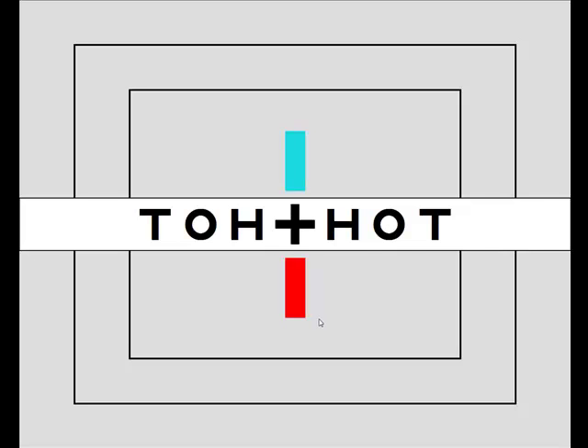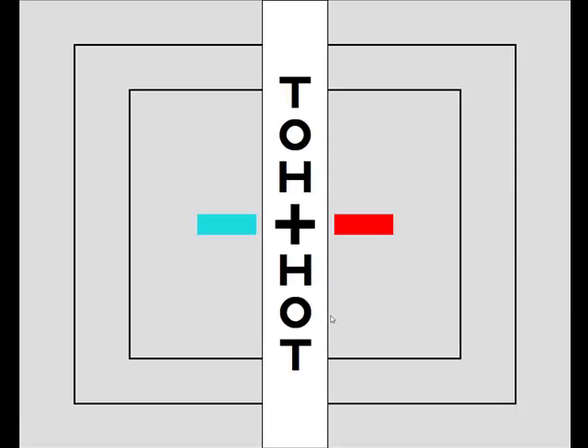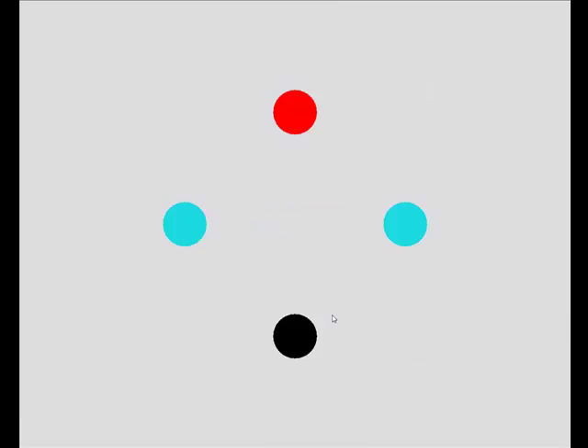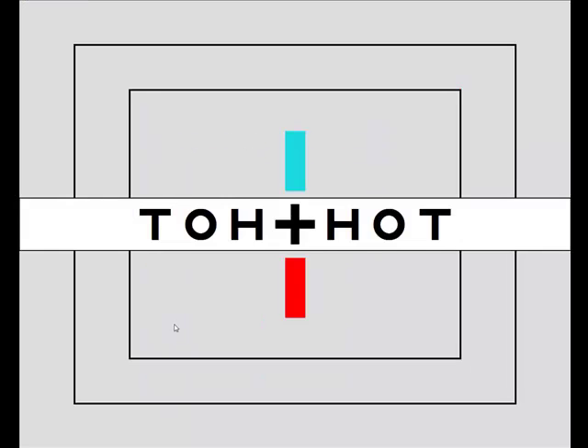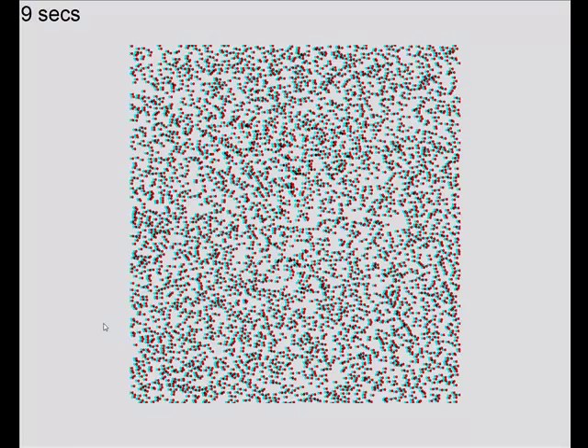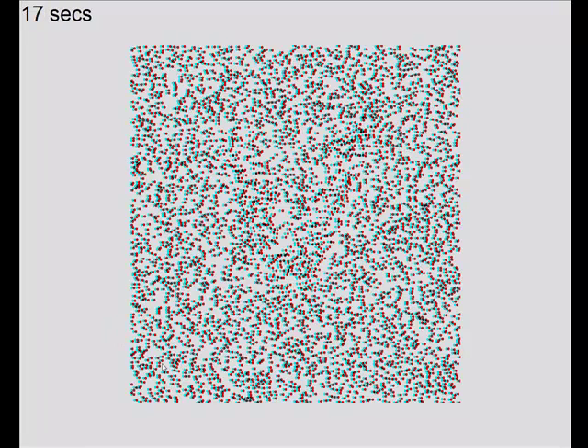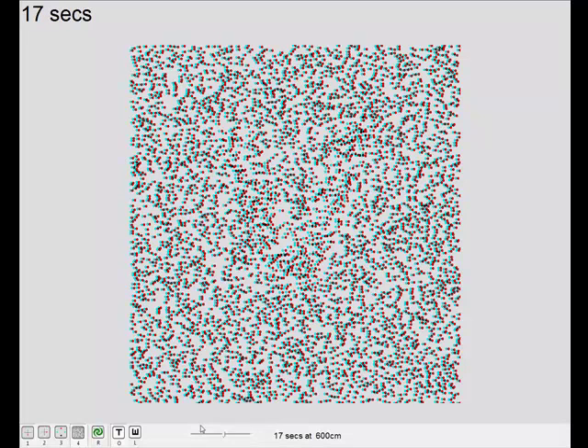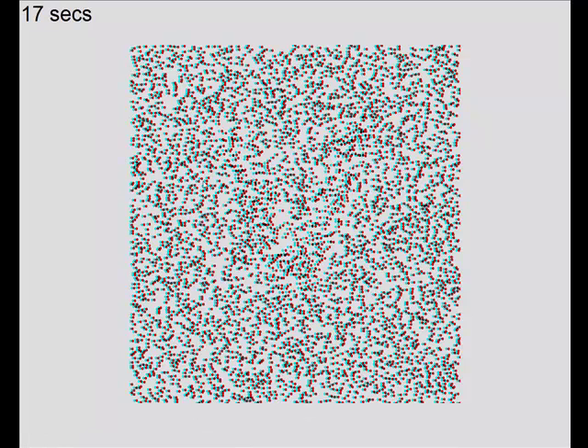This is for measuring horizontal fixation disparity, vertical fixation disparity, the Worth Four Dot test. And this is a distance random dot stereogram. If the patient is wearing the red and green visors, they'll see a shape standing out from the screen. These are generated dynamically. By using the up-down arrow keys on the keyboard or the scroll bar in the secondary toolbar, you can make the letters come out from the screen or into the screen.